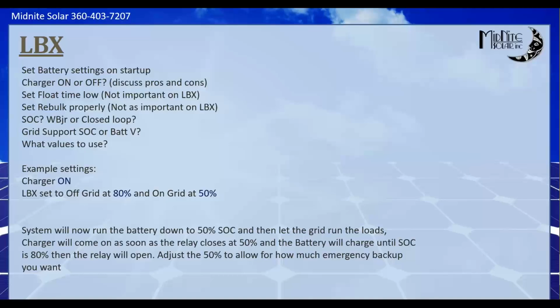I would set LBX to go off grid at say 80% state of charge, and back on grid at 50% state of charge. So what happens in this example is the system runs with the relay open in an off-grid state, because it's ignoring the utility grid, until the battery drops down to 50% state of charge. When it hits 50%, it closes the relay, and the grid runs the loads. If the charger is on, like in this example, the charger comes back on too and charges the battery back up. It keeps charging until it hits 80%, then the relay opens again, and it keeps repeating that process, which is why I say you really don't want to run the charger in these modes if your goal is truly grid curtailment.